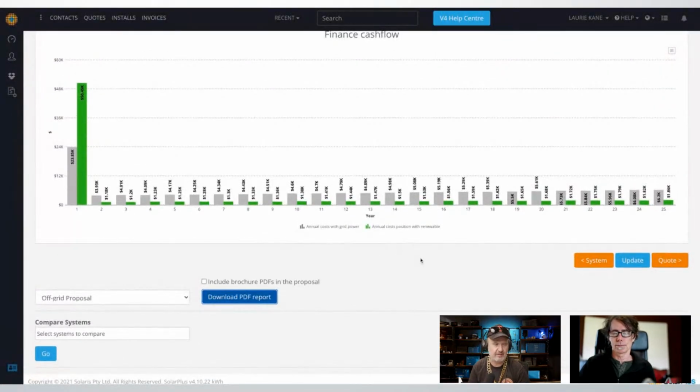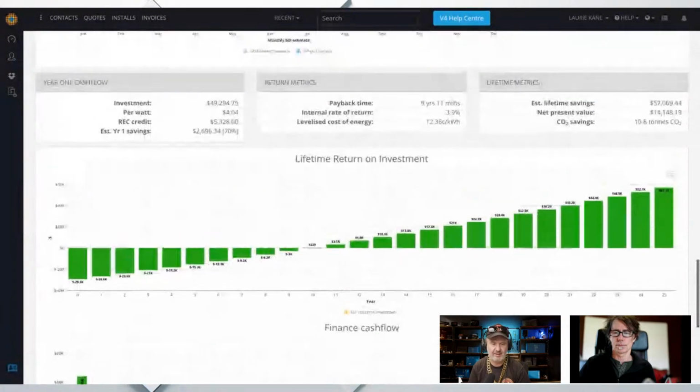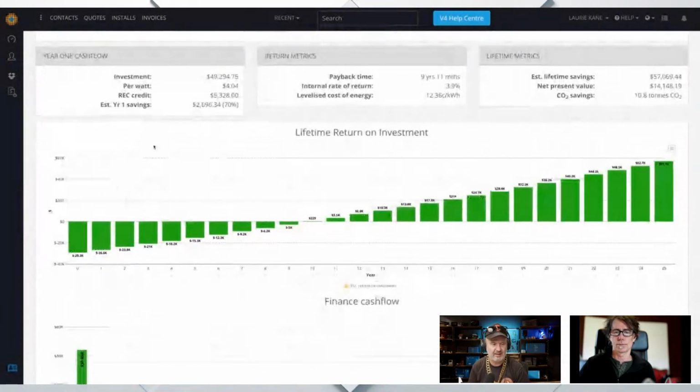I think your connection cost there, certainly for this area, is quite conservative too. So, 23,000 is a fairly low figure. You probably have to have capacity in the transformer already, the house close to the road. And of course, there'll be the reticulation from the point of connection to the house as well, which, depending how far that is. So, sometimes the payback is day one.